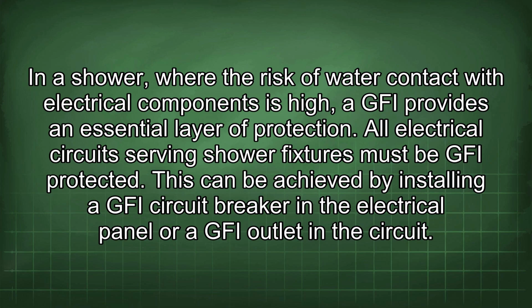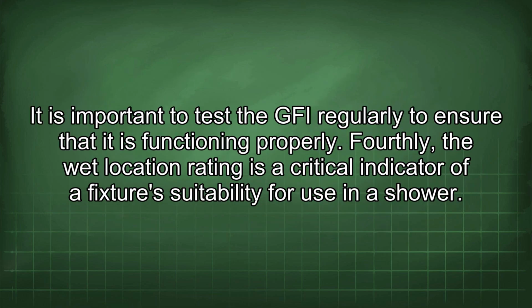In a shower, where the risk of water contact with electrical components is high, a GFI provides an essential layer of protection. All electrical circuits serving shower fixtures must be GFI protected. This can be achieved by installing a GFI circuit breaker in the electrical panel or GFI outlet in the circuit. It is important to test the GFI regularly to ensure that it is functioning properly.